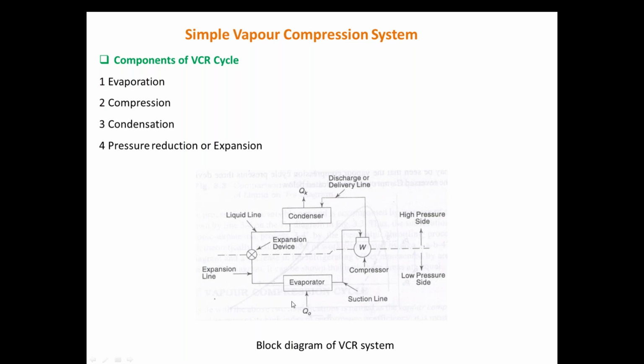Q0 is the desired heat that we have to remove from the space that we want to maintain at a lower temperature than the surrounding. So our target is the evaporator, where Q0 is the amount of heat removed, and then the refrigerant, after absorbing heat from the evaporator, gets vaporized or evaporated, and that vapor is then supplied to the compressor.